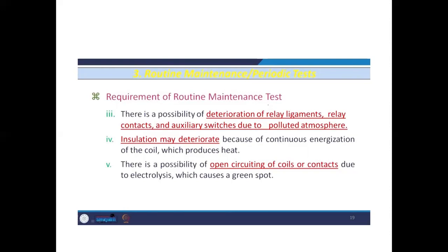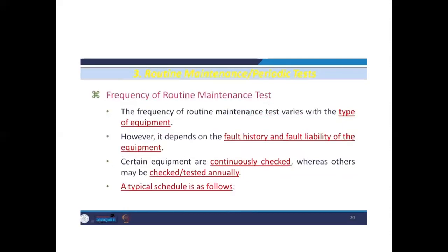So this insulation should be checked by the insulation test. And there is a possibility of open circuiting of coils or contacts due to the electrolysis, which causes a green spot. Okay, this is the chemical effect. So the chemical deterioration also affects the operation of the relays. Okay, so this should also be checked.